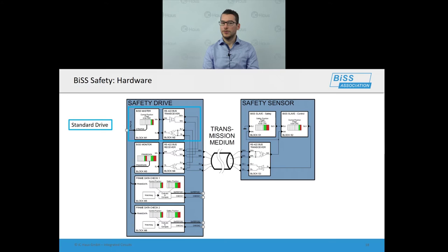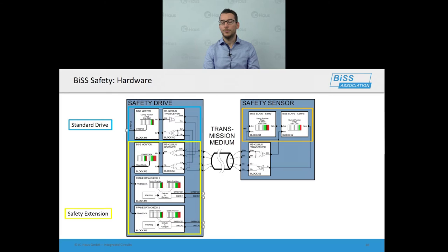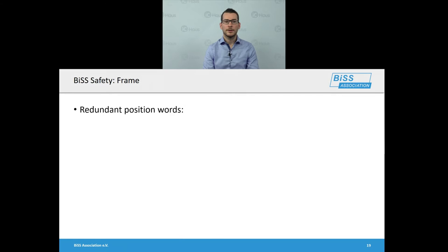Here is a hardware example. There is a safety drive consisting of a standard BiSS drive which contains the BiSS master, extended by a data and safety extension. The safety block contains a BiSS monitor which observes the data lines and performs frame data checks. On the slave side, a BiSS safety sensor contains two independent position words generated by one or two sensors. There is a control position word used by the standard drive for motor control, and both the control and safety position words are used by the safety extension to perform safety checks.